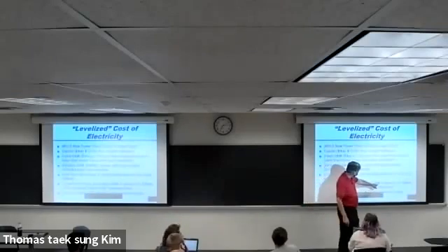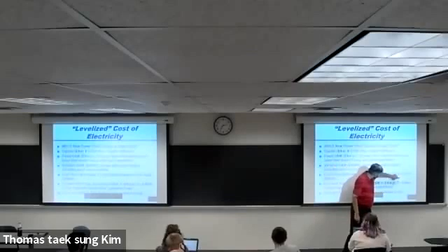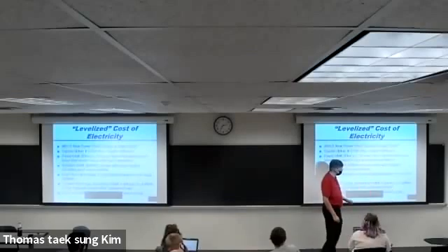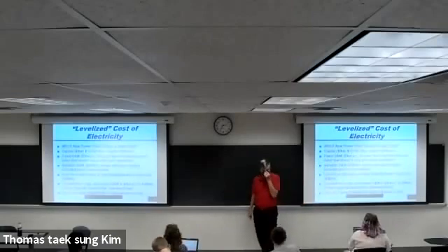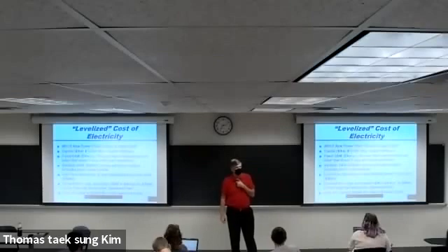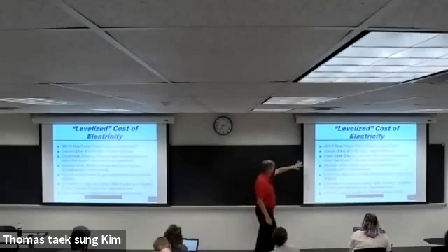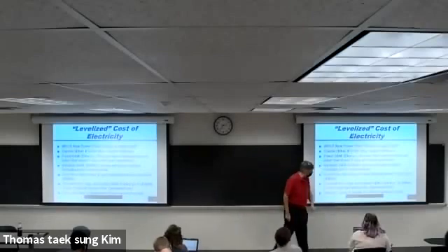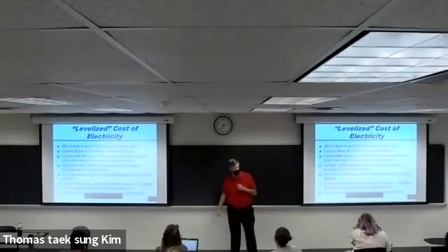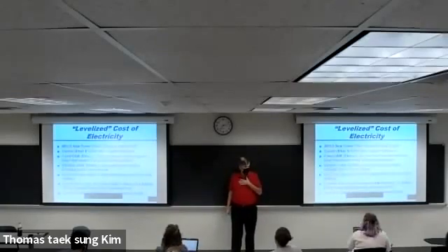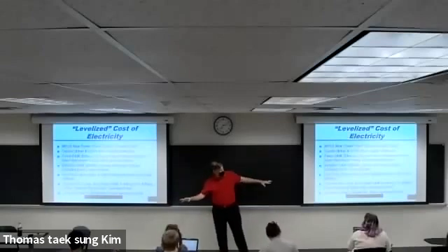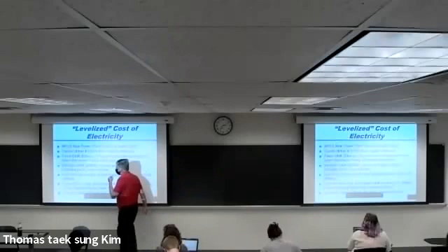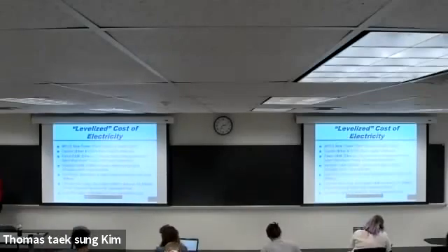And all you're doing is multiplying dollars per kilowatt year by the number of hours over the year, and that will end up giving you dollars per megawatt hour, also by converting kilowatts to megawatts. So once you've got all these in dollars per megawatt hour, you sum them all up. That's the total levelized cost for that power plant. Now I didn't go through all the details of that, but I gave you the big picture. Let's go to something more specific now.